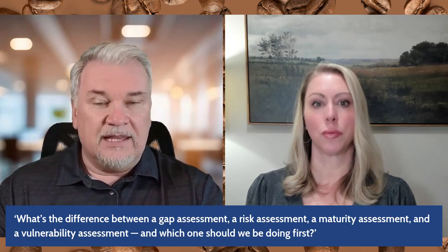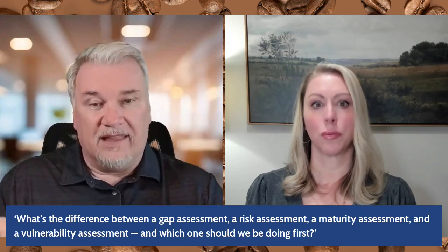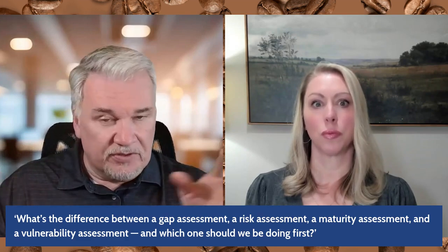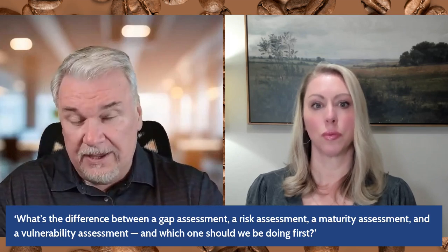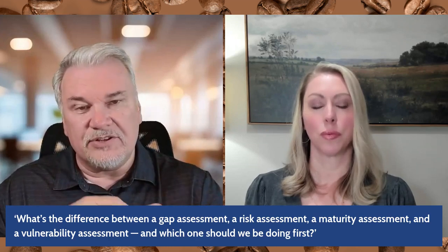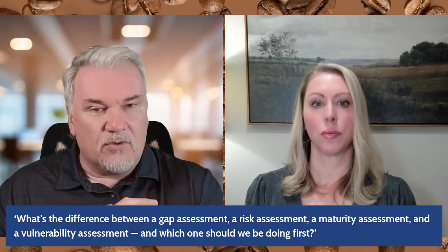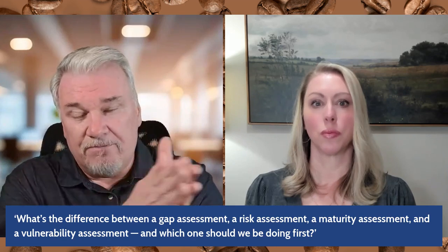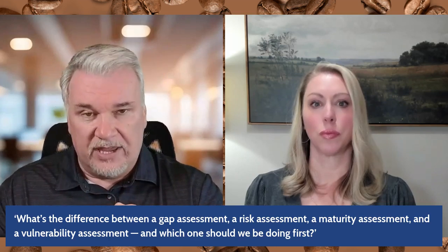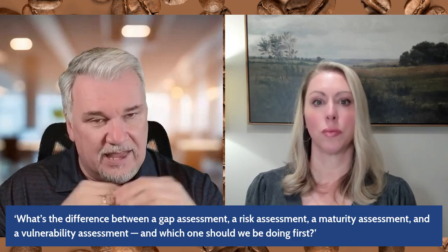Now, at the plant level, especially for some critical operations, this is where utilizing a risk assessment is a good idea, to understand your baseline and the risk of your cyber physical system and the process that's being automated, whether that's a chemical facility, a water treatment facility, or whatever the case may be. There's multiple ways of approaching that risk calculation. Some will use the classic likelihood times threat times impact to get to a risk score. Now with cyber-informed engineering, there are more techniques around impact. And one of the really useful tools available to us is the cyber PHA, or process hazard analysis, giving us the bow tie methodology. All of these are different types of risk assessments. So risk assessments definitely have a place.